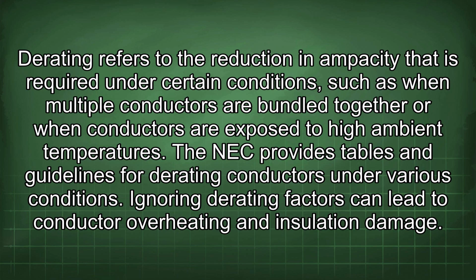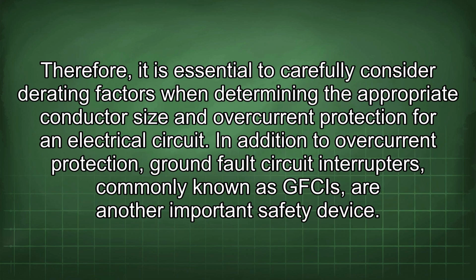The NEC provides tables and guidelines for derating conductors under various conditions. Ignoring derating factors can lead to conductor overheating and insulation damage. Therefore, it is essential to carefully consider derating factors when determining the appropriate conductor size and overcurrent protection for an electrical circuit. In addition to overcurrent protection, ground fault circuit interrupters, commonly known as GFCIs, are another important safety device.